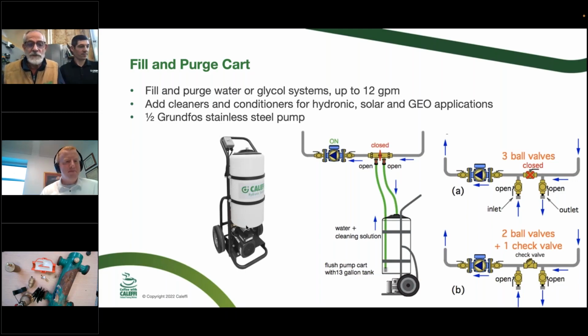Typically 2 to 4 feet per second is the accepted velocity in a hydronic system. What we've learned from the professional purgers is you've got to get over 5 feet per second to start moving stuff like dirt or gloves or Lego or whatever it might be. Your circulator is probably not designed to do that.